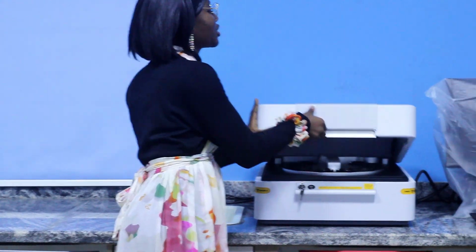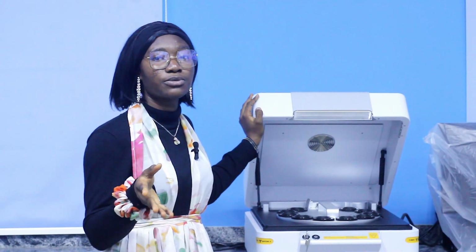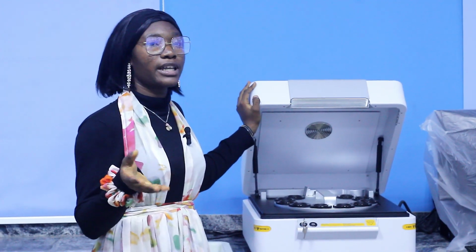This is the EDX X-ray fluorescence machine, also known as the XRF machine. It is used to provide fast and non-destructive elemental analysis, from ppm to 100% concentration, of solids, liquids, and metals. It detects elements ranging from light elements, transition metals, to heavy metals. For light elements, you have examples like calcium and potassium. For your transition metals, you have examples like zinc and iron, and for your heavy metals, you have gold and tin.